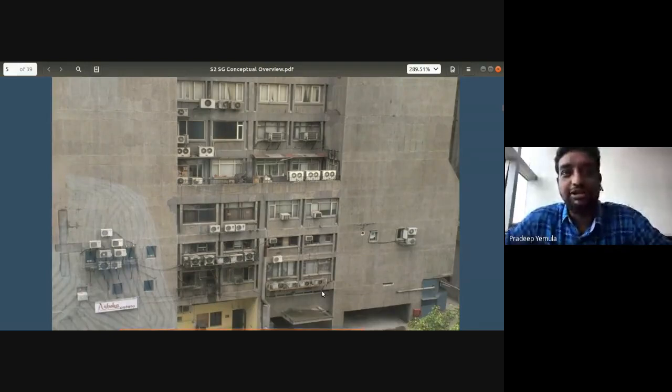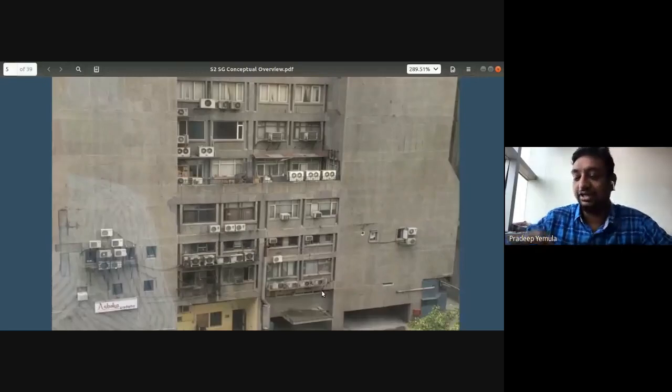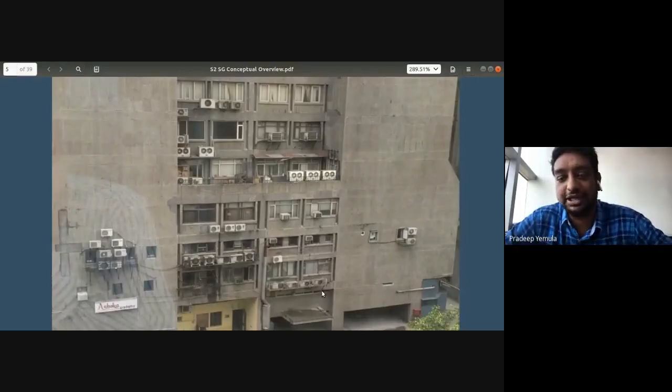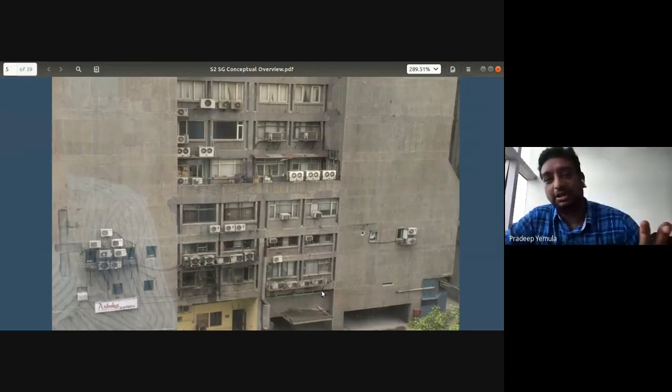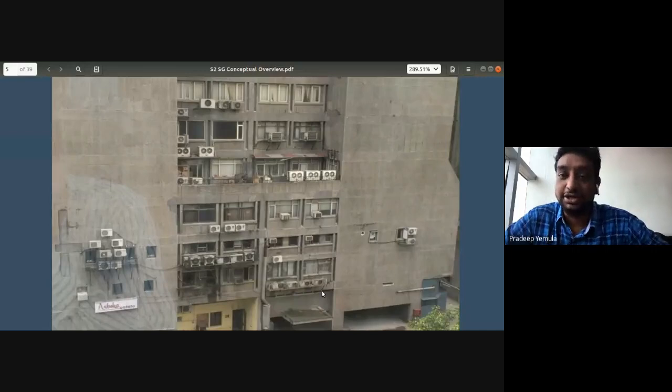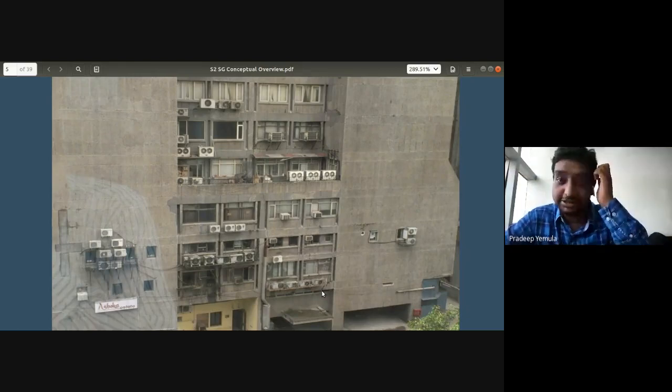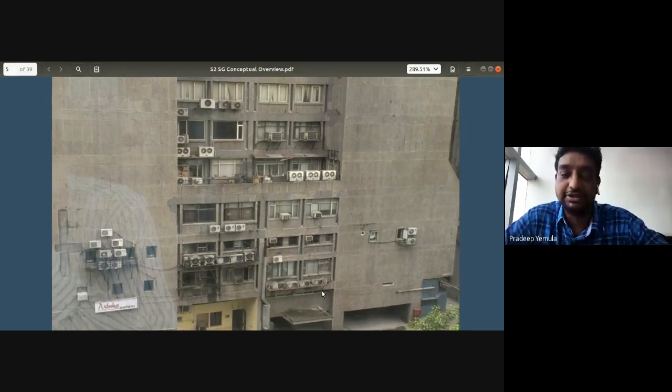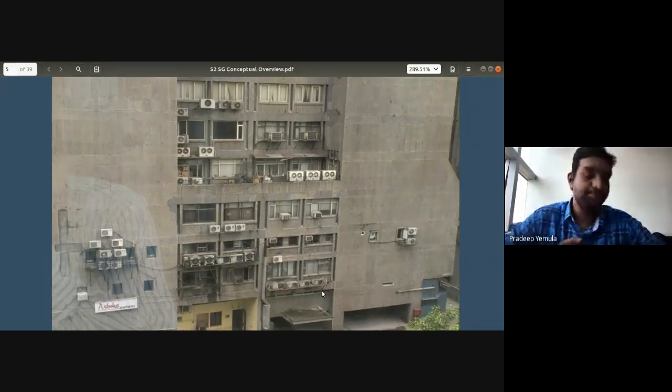Now, it could also be argued that you can control the AC. If there is nobody in certain rooms, you can control the central AC such that it won't cool that particular room where nobody is there. So such kind of things can be possible. And cost-wise also, the cost of 100 ACs, each of 1 ton, will be more compared to the cost of one AC which is 100 tons capacity. So a larger AC will have a lesser cost. So cost-wise, central AC will be better.